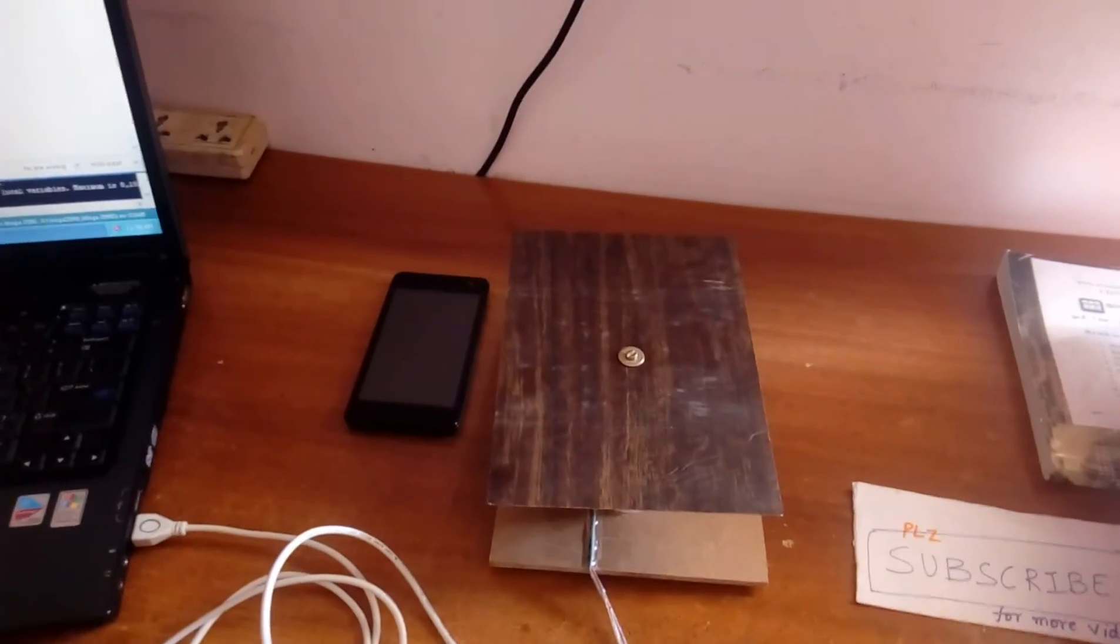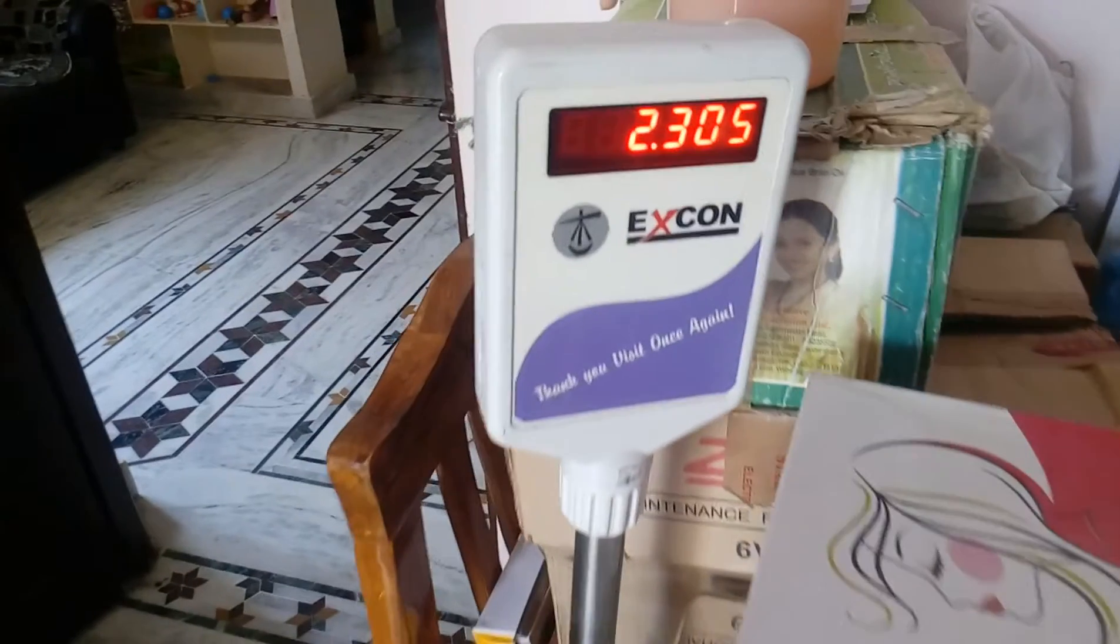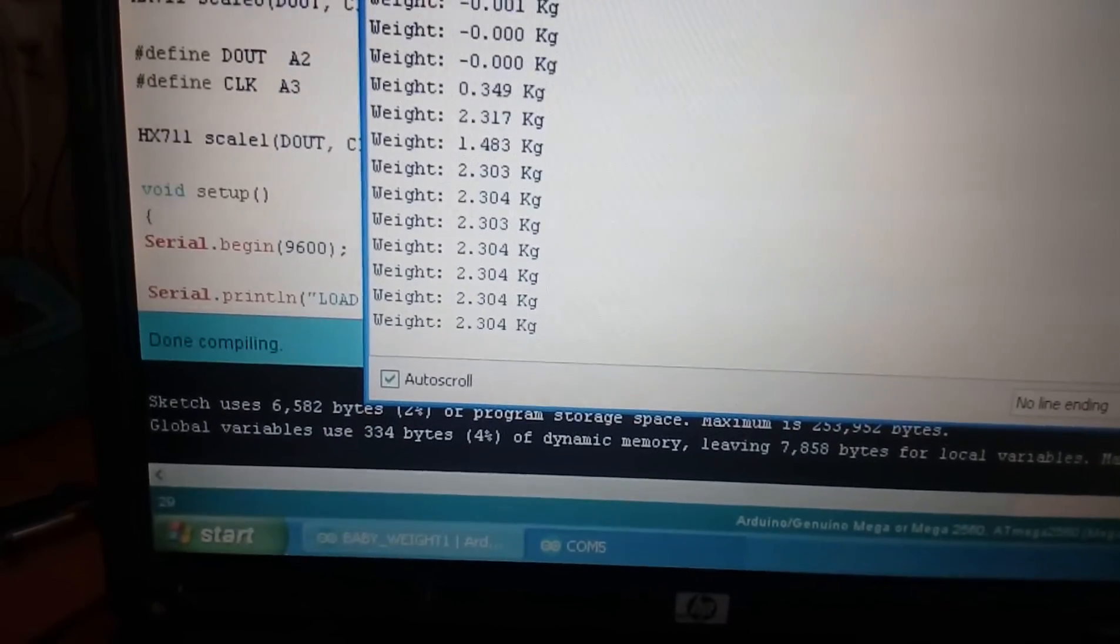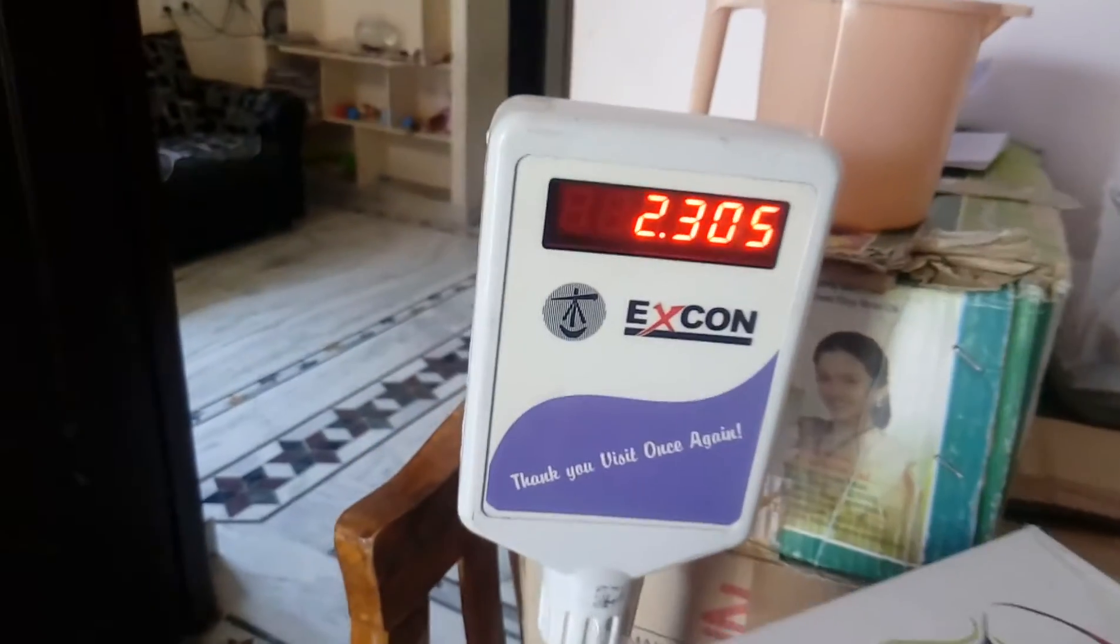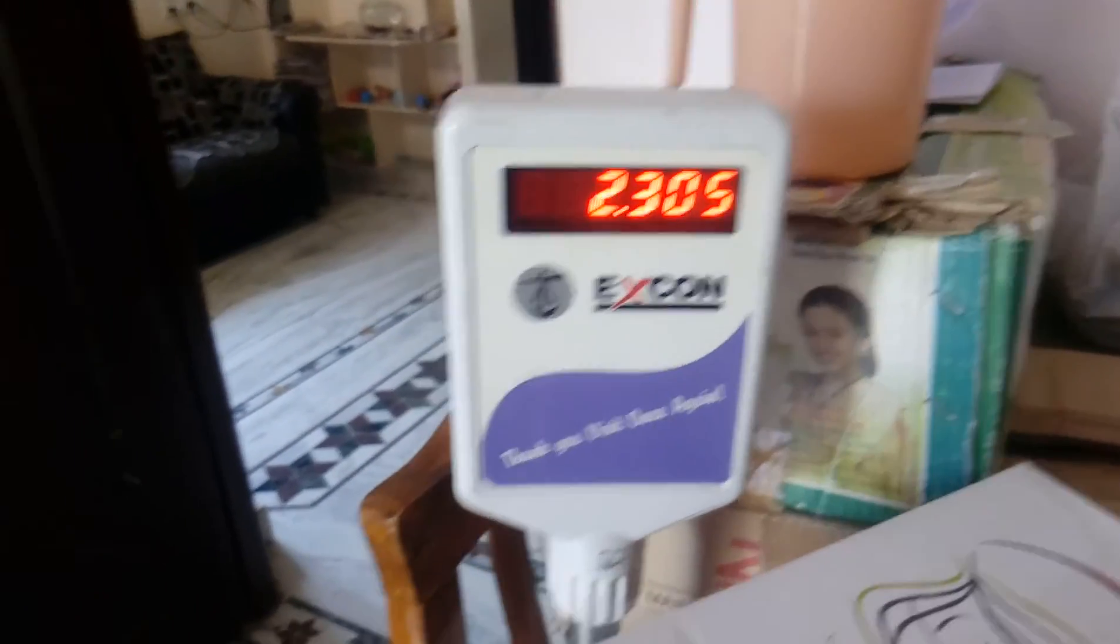Now I am going for 2 kg. 2.305, 2.302, 2.303, 2.304. The readings are around 2.303 to 2.305, within 1 percent accuracy.